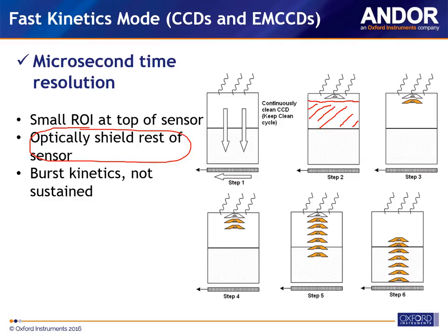So then you acquire your image in the, say, top number of rows, and then once that's done, you do a vertical transfer of the image into the 40 rows beneath that. Again, this happens very fast. Vertical parallel transfers happen typically on a sub-microsecond to say up to 10 microseconds per row timescale, depending on the sensor type, but very fast dynamics irrespective.